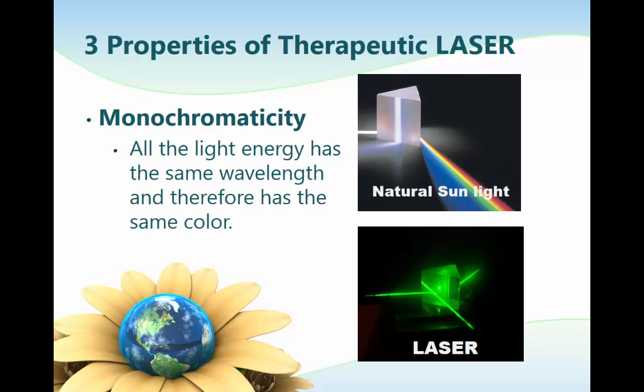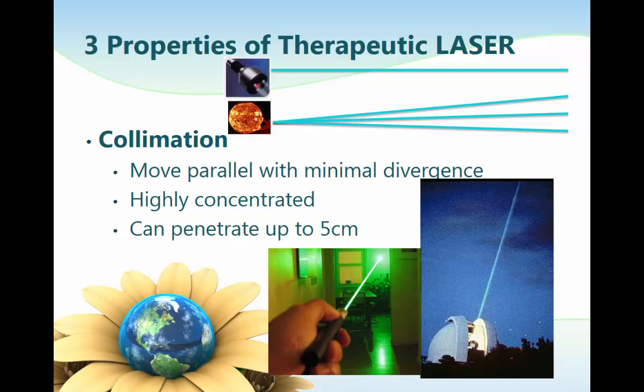Monochromaticity is defined as having a single frequency and therefore a single color within the light spectrum — all of the light energy has the same wavelength and therefore the same color. Laser light is collimated because it diverges very little as it travels through space. The photons move parallel with minimal divergence, meaning the beam is highly concentrated. Due to collimation, the laser beam can penetrate up to 5 cm in human tissue.